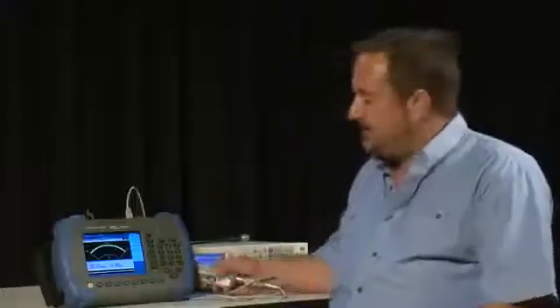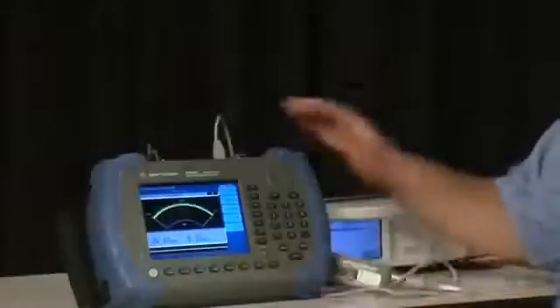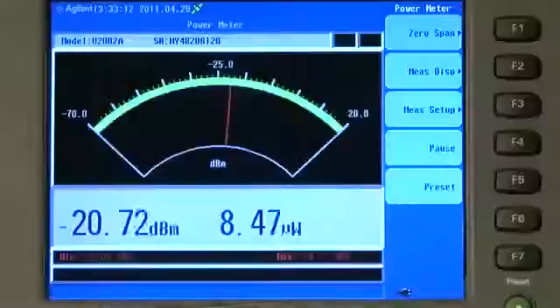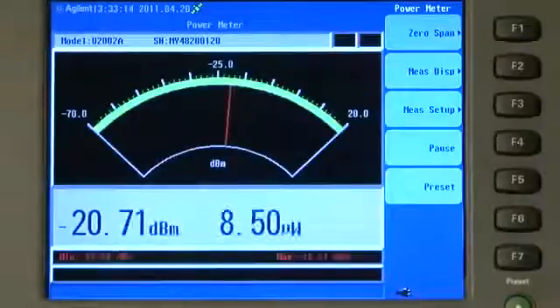Secondly, a power meter is always going to make a far more accurate measurement than any spectrum analyzer ever can. So with our handheld spectrum analyzer and the U2000 sensor, we can make RF level measurements with the ultimate accuracy.